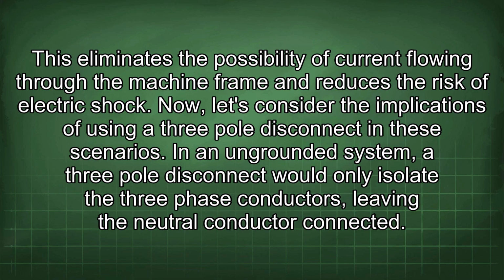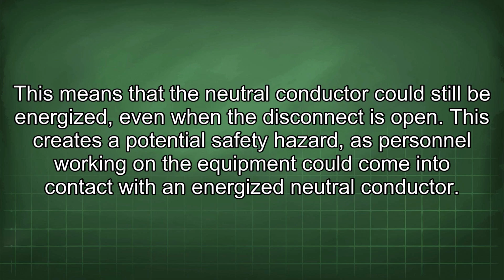Now, let's consider the implications of using a 3-pole disconnect in these scenarios. In an ungrounded system, a 3-pole disconnect would only isolate the 3-phase conductors, leaving the neutral conductor connected. This means that the neutral conductor could still be energized even when the disconnect is open. This creates a potential safety hazard, as personnel working on the equipment could come into contact with an energized neutral conductor.